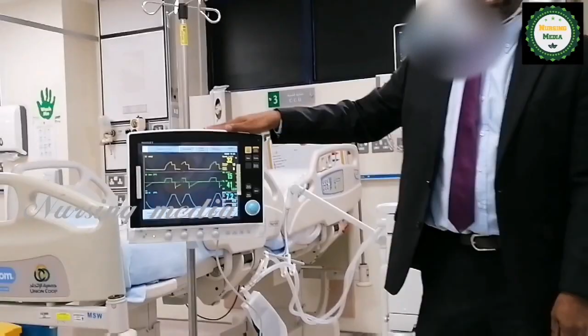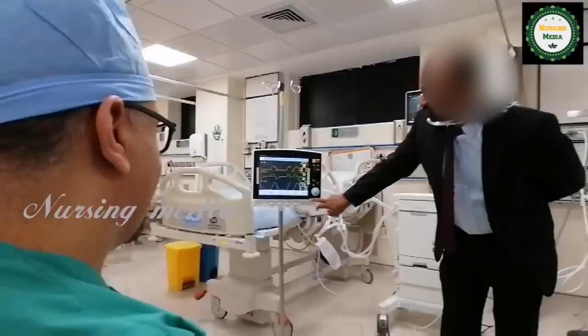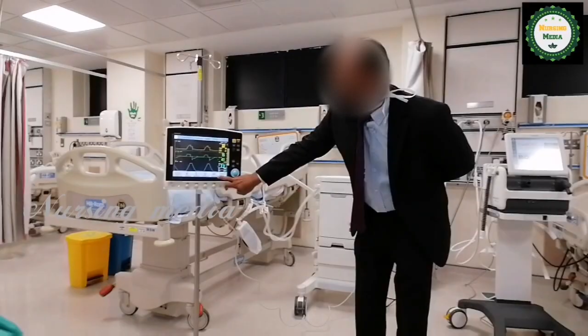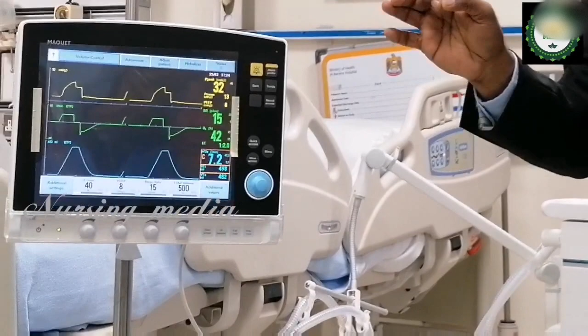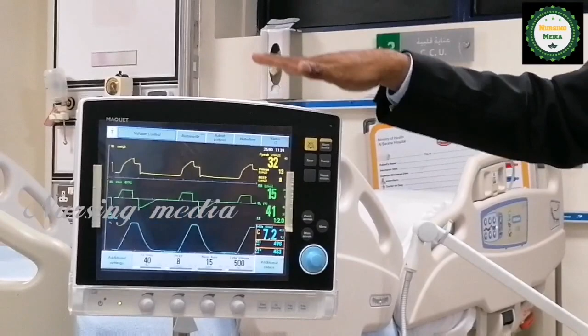That's the thing. Yeah. See, we set volume control, we are setting 500 ml, it's delivering 498, it will deliver 500. It's extremely accurate. You don't see that in any other ventilator. I'm not exaggerating, by the way, I'm a clinical person, same as you all. It's very accurate. It has an extremely superior leak compensation also. Even if you have an uncuffed tube, a big leak, it will ventilate without any problem.